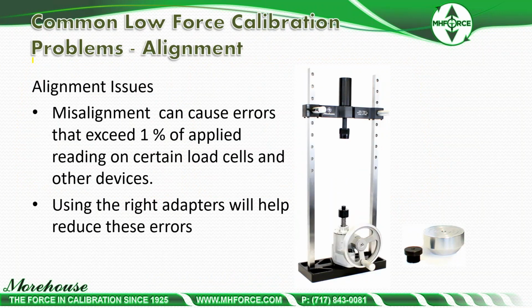So the other thing, misalignment can cause errors that exceed 1% of applied reading on certain load cells and other devices, and just using the right adapters will help reduce these errors. Like, you really have to center this machine.